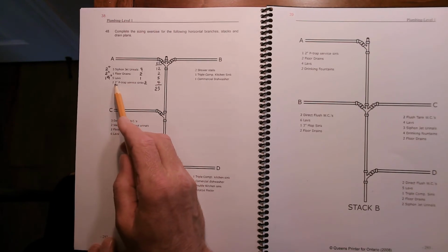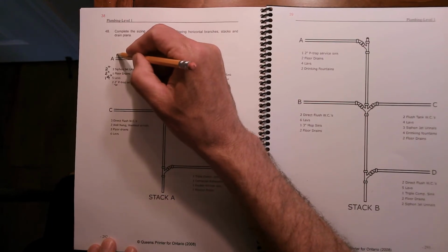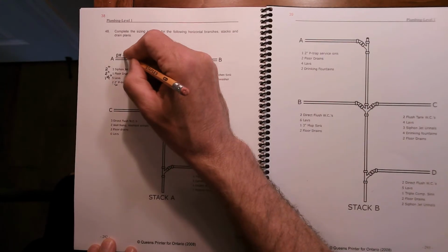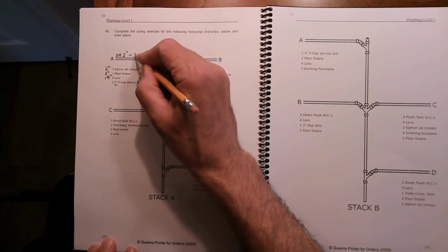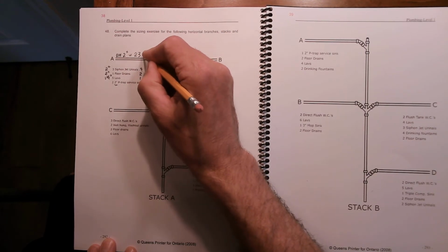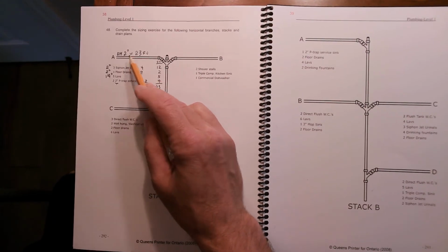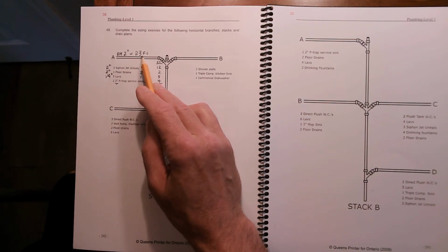And your largest size on this branch is 2-inch, so your default minimum. I like to call this the dumb size because it's only the starting size. The dumb size, 2-inch with 23 fixture units. So then you'll go to a table, and we're not doing the tables today, but you'll take this fixture unit to that table and ask yourself, can 2 inches handle this much water?